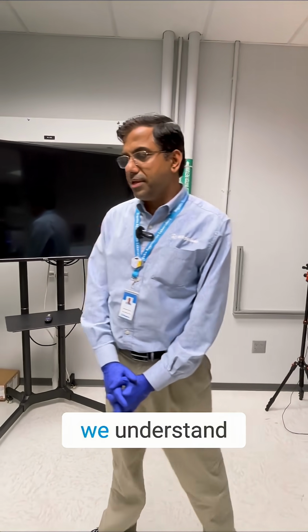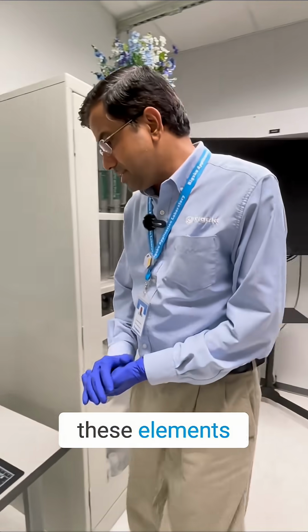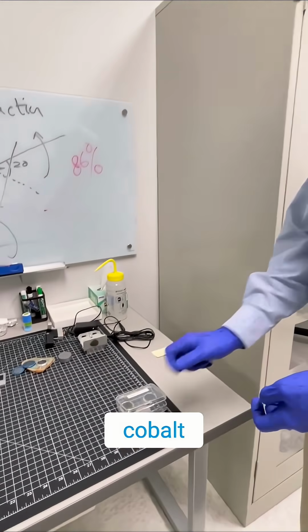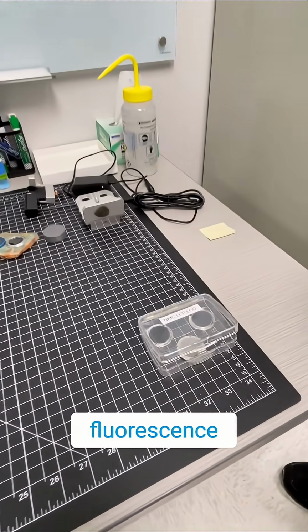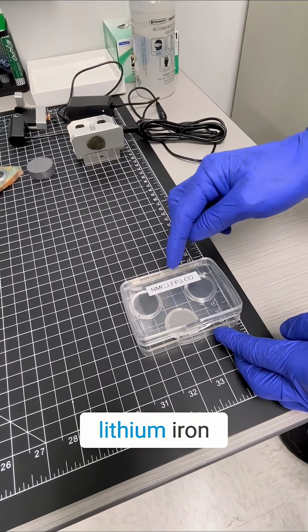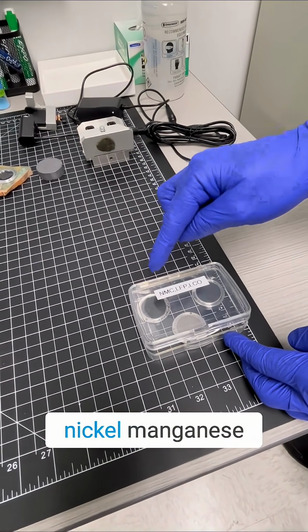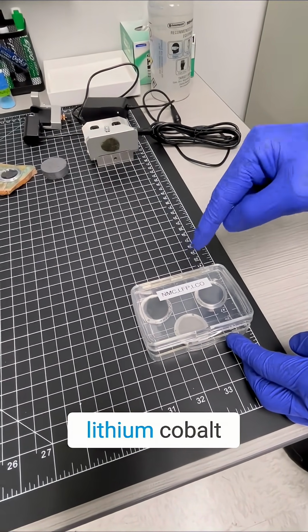Show me how to measure cobalt containing samples on the MiniFlex? Sure, Aya. So we understand some of these elements such as nickel, manganese, cobalt, these have high fluorescence. NMC, LFP, lithium iron phosphate, nickel manganese cobalt, lithium cobalt oxide.